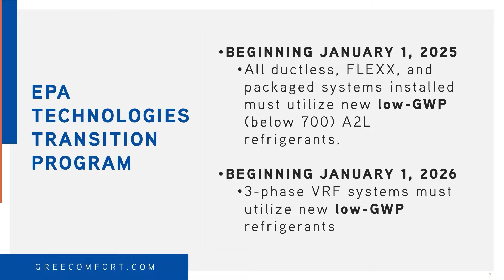How we'll be handling that is GREE has decided to go to R32. Why did we choose R32? Well, obviously R32 has a low global warming potential, below the 700 threshold set by the EPA. R32 is also shown to have more capacity than 410A and more efficiency, so we'll have better performing units out there. R32 also doesn't contain any of those dangerous fluorine forever chemicals like some of the other refrigerants out there.